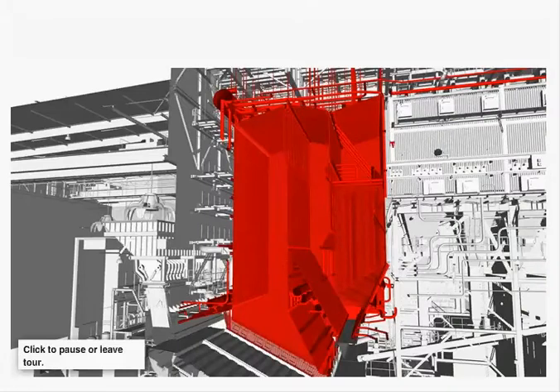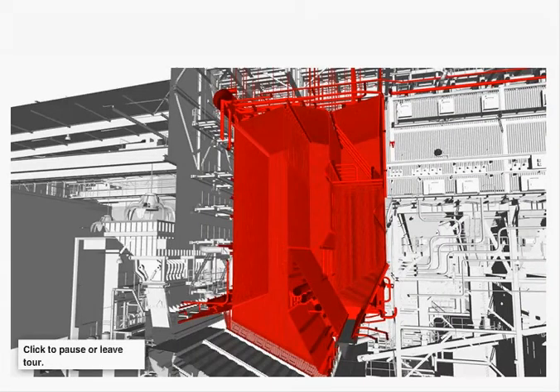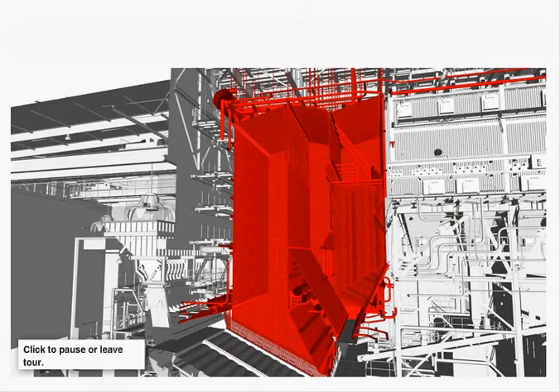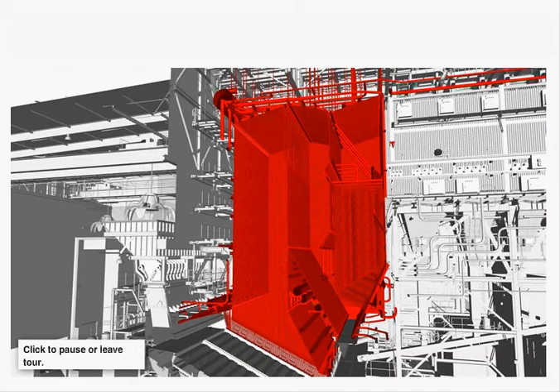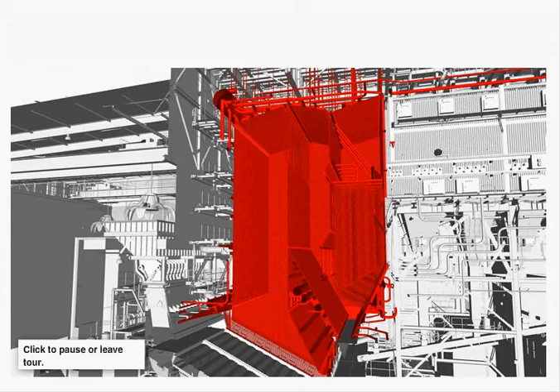All our boilers are designed by our CFD specialists in order to achieve the best flow and temperature conditions. In order to protect the radiant part of the boiler, we use Inconel, which protects against corrosion. Our Inconel cladding is based on the latest CMT, cold metal transfer technology, ensuring high quality and a long lifetime. Our iron content in the Inconel is very low, typically less than 3%.